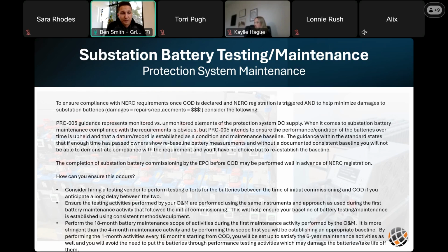Or the best solution we've seen, and the recommendation that works most often, is to have the first battery maintenance activity performed by the vendor through the O&M after you're operational be the 18-month battery test rather than the 4-month test. The requirements of the standard are 4 months, 18 months, and eventually 6 years. So if you perform the 18-month test right out of the gate, you can avoid the need to perform extra testing and potentially damage the batteries by putting more strain on them than necessary.